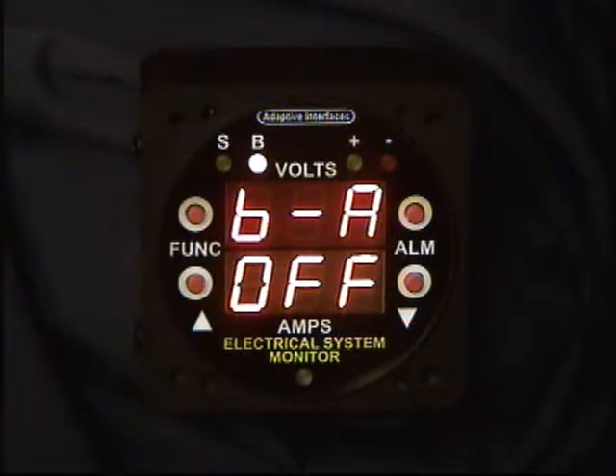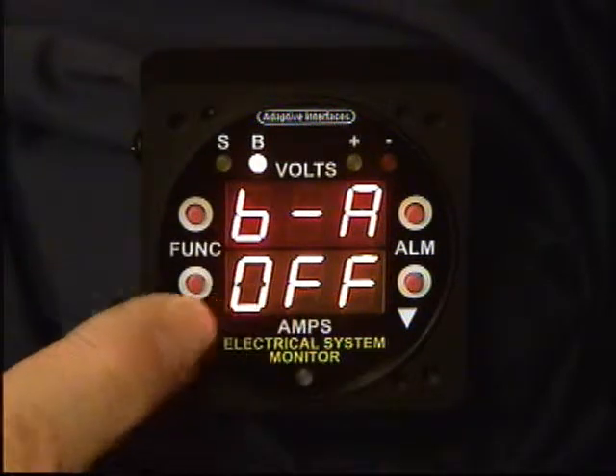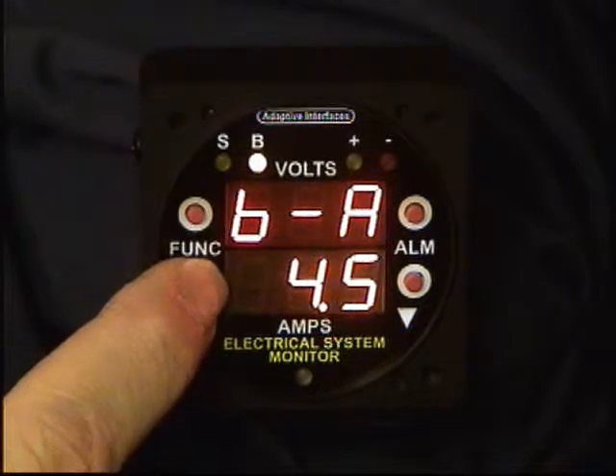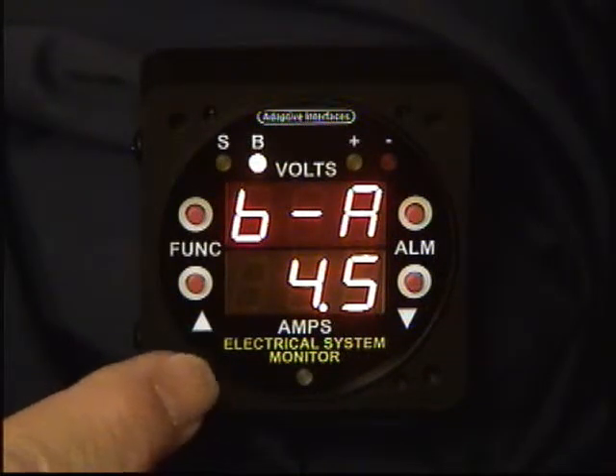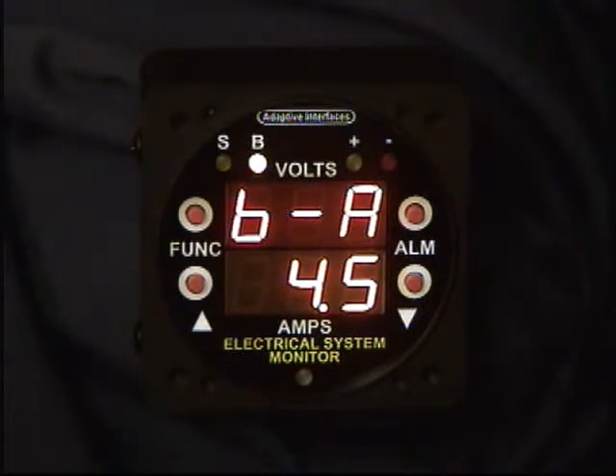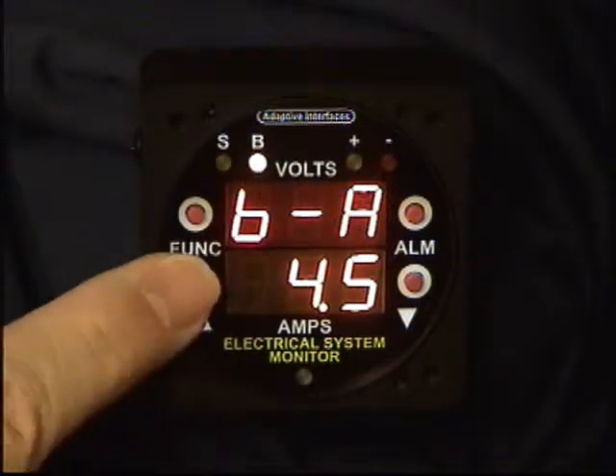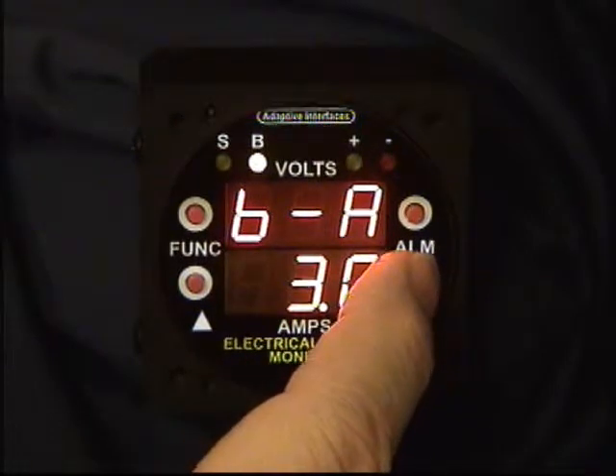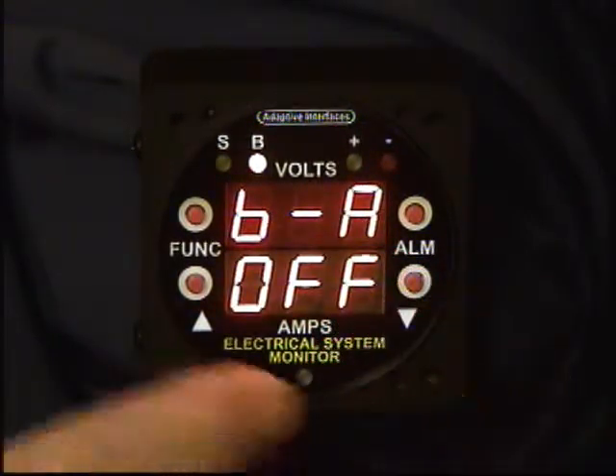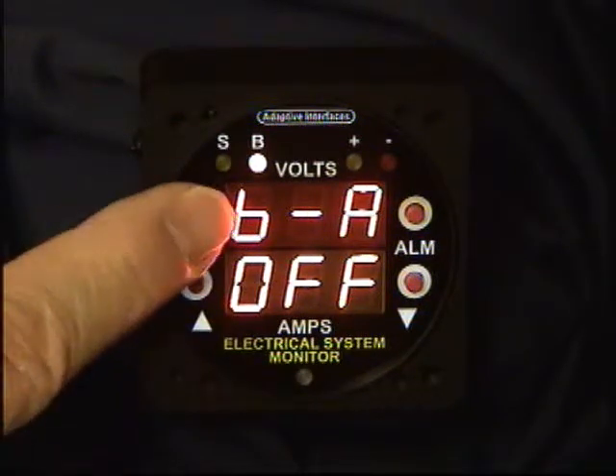Next function is the battery alarm level, and if it's turned on and set to a value such as, say, 4.5 amps, if the battery charging current exceeds 4.5 amps, the instrument will show an alarm condition. Also, if it shows a negative current, in other words, the battery is discharging through the alternator, which would indicate that the alternator is not working and not charging the battery, that will also set an alarm condition. But again, it gets very distracting using this alarm, so we'll just go ahead and leave it off.